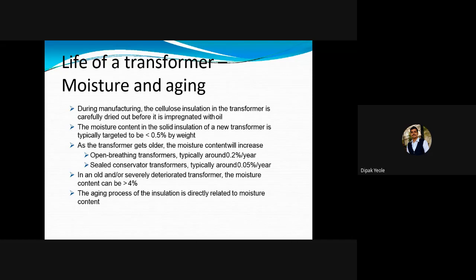Open breathing transformers typically contain around 0.2% moisture per year, and sealed conservator transformers typically around 0.05% per year.